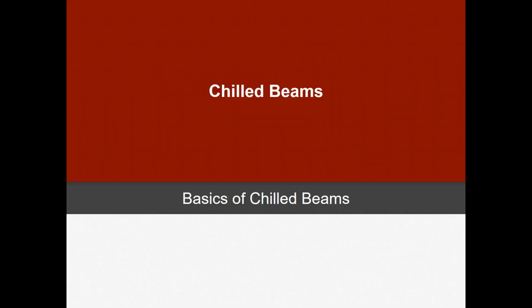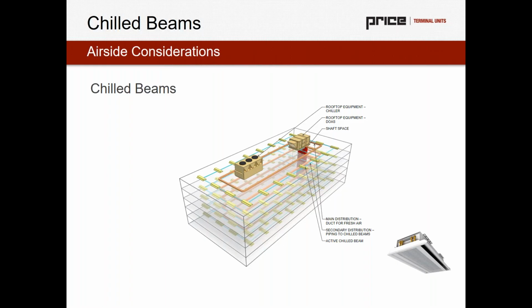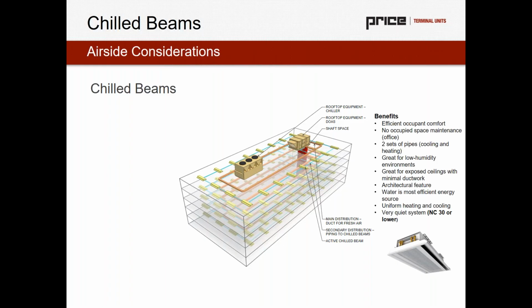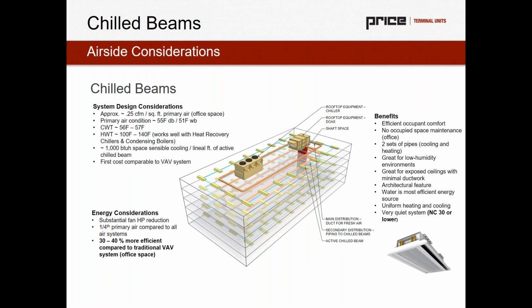So I just want to go through a brief review of chilled beams and fan-powered chilled water terminals, and then we'll look at utilizing those two systems together. We're first looking at chilled beams here, and the big thing I want to lay out is the general system design, because we're going to see a motif as we move through, looking at this system, looking at fan-powered chilled water terminals, and looking at the two together.